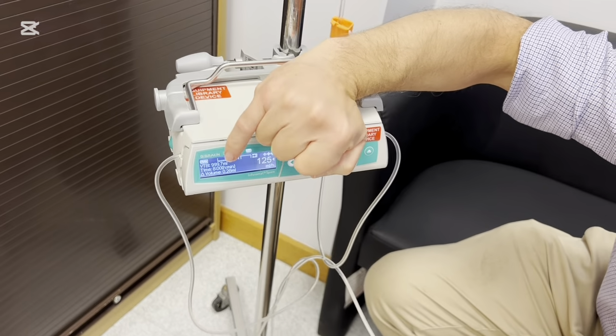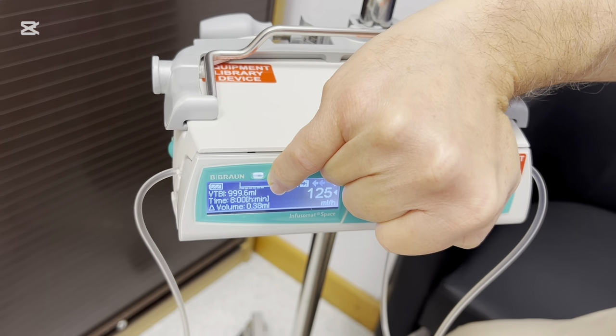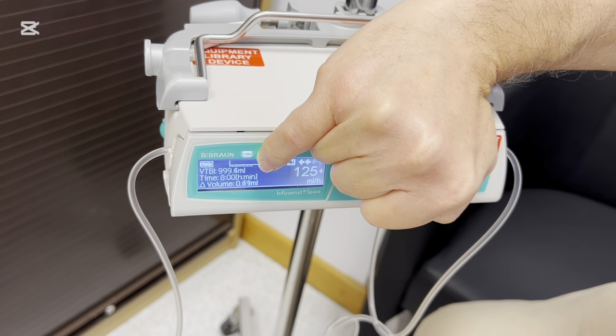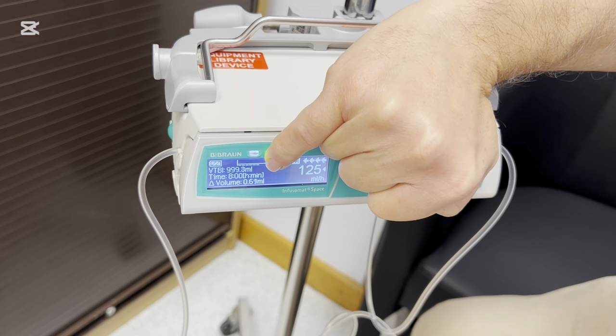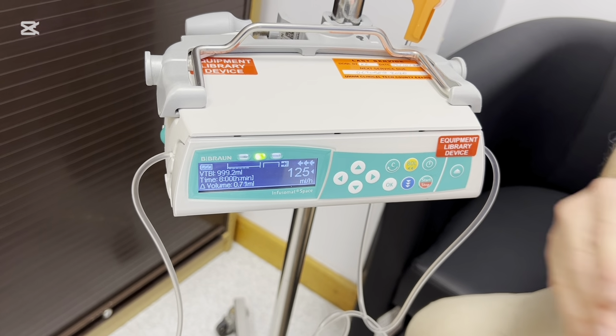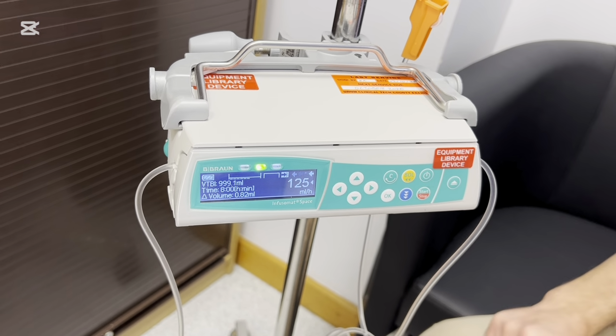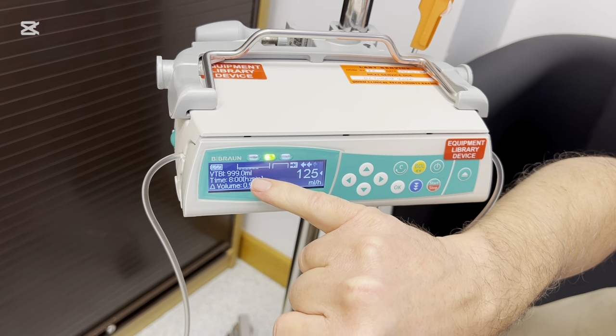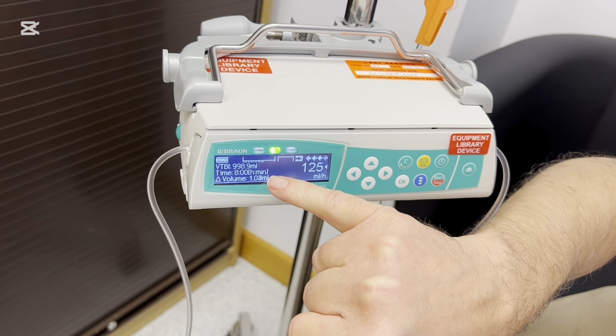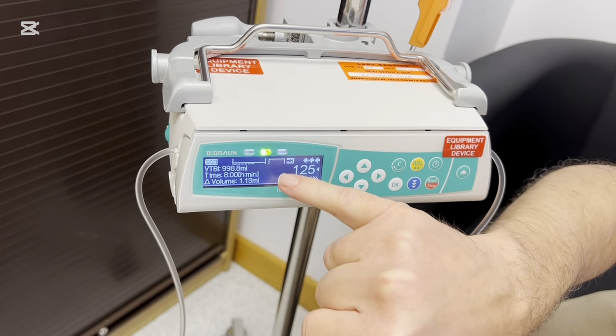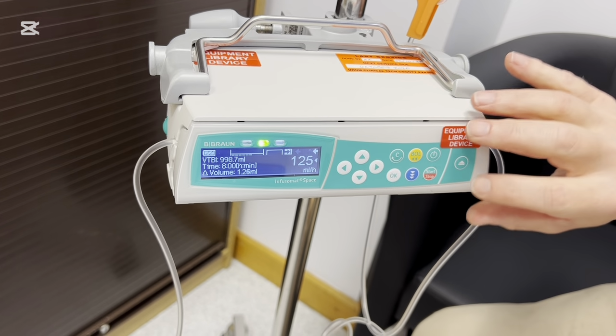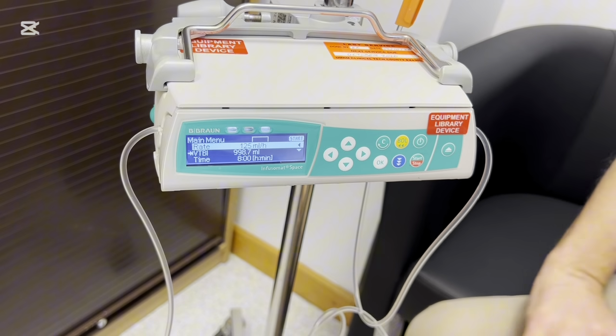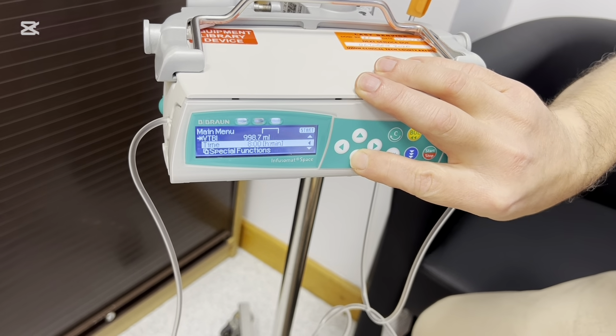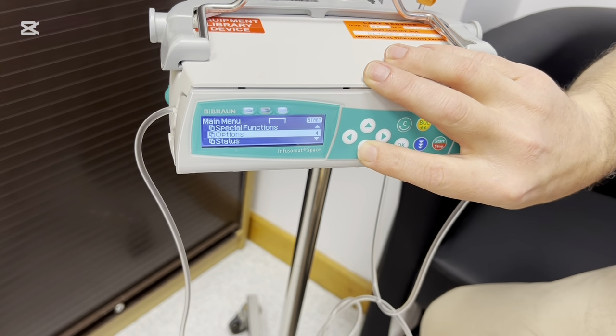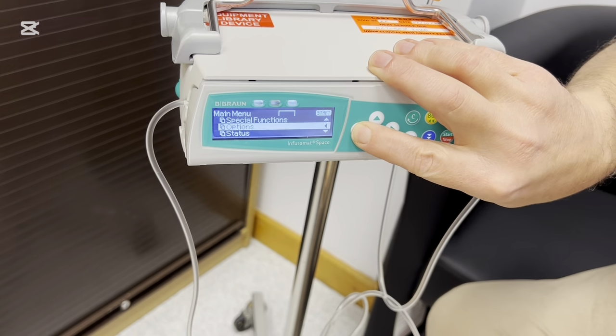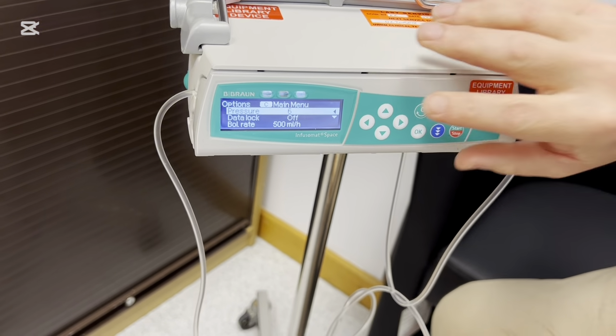Along here is you can set the pressure, the occlusion pressure against which the pump will deliver against. So we can go into the options. So if you're pumping through a large peripheral cannula, then you want this set to the lowest, a low value. If you're pumping through a central line or a long tortuous line, then you may want a higher pressure selected. So the rationale for these is to try and reduce the risk of extravasation, but you're never going to remove that risk completely.